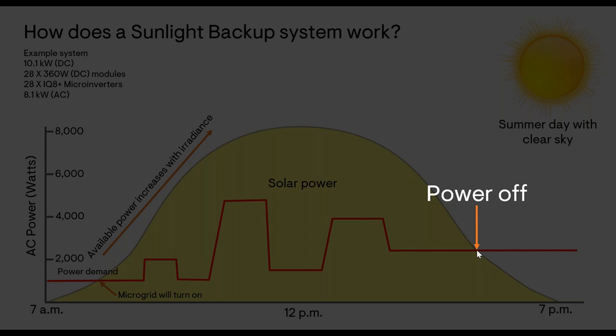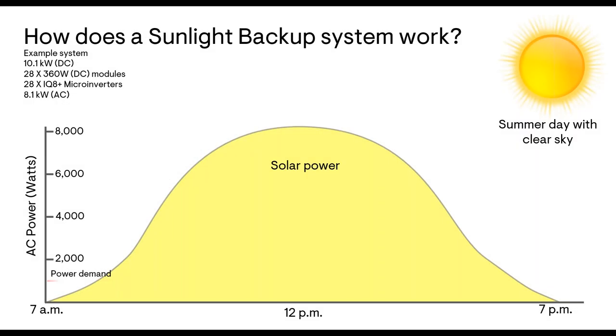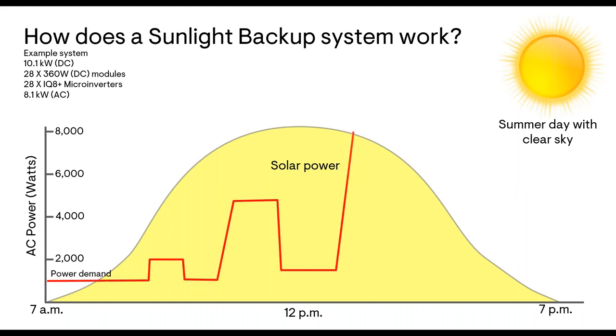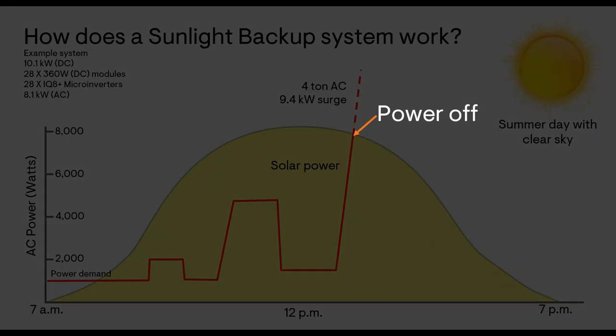There's no buffer there, there's no battery. So for it to work, you need the red line here, which is the power demand of the house, to be underneath the power output for the solar array. So if we're looking at something heavy, like if someone says, I want to back up my AC, my air conditioner unit or my well pump, something that might have a big draw in the beginning as it's turning on, that inrush or surge might overpower what's available from sunlight.